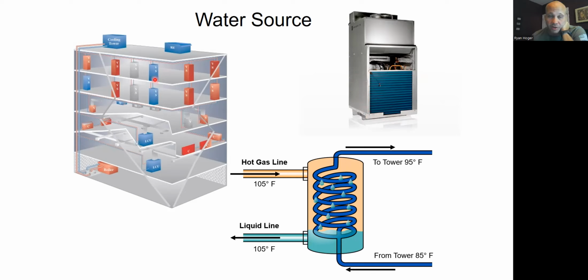Some of these zones in blue are showing that they need cooling. Other zones are needing heating, and they're dumping water onto the loop. This exact machine is the exact same thing we're doing with these chillers. But in this case, when it's a water source heat pump, that usually implies we're doing it on a zone by zone level, and there's a water loop running around the building. When it's a heat pump chiller or a heat reclaim chiller, it's implying I'm doing it at the building level. And this machine, there's one machine in the central plant being switched over.